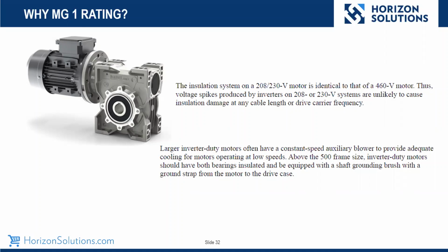The larger inverter-duty motors usually have a blower on them to provide the extra cooling that you need at low speeds. And remember, MG1 strongly suggests that you need both bearings to be insulated on the load and the fan end, and you really need the grounding shaft also. That's a requirement with the MG1 motors at the higher horsepower, 500 frame and above. Next slide.